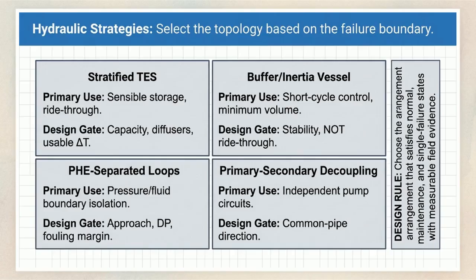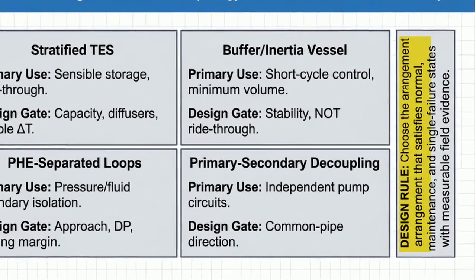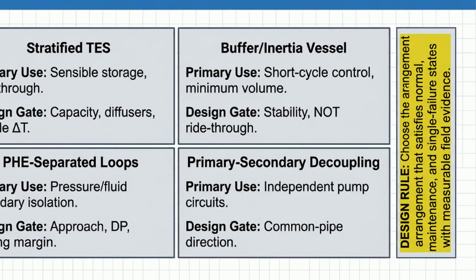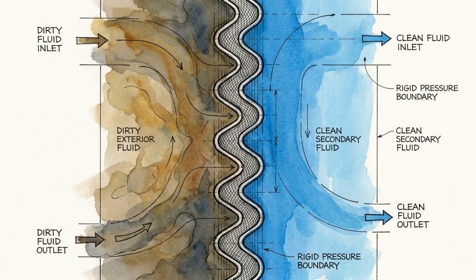This matrix outlines the four primary hydraulic strategies: stratified storage, buffer vessels, plate heat exchanger separated loops, and decoupling. The design gate dictates which arrangement matches a facility's specific failure criteria. Plate heat exchanger separated loops establish a hard physical wall in the system. This provides a strict pressure boundary that completely isolates the potentially dirty exterior primary loops from the pristine secondary loops serving the data hall.